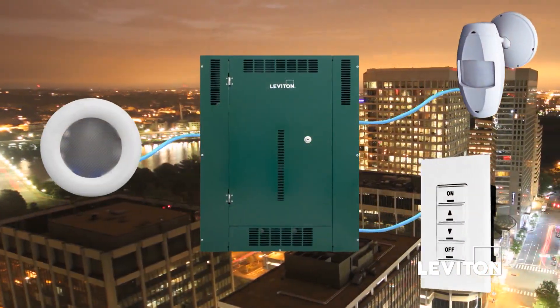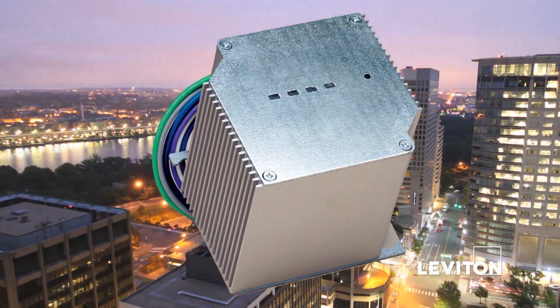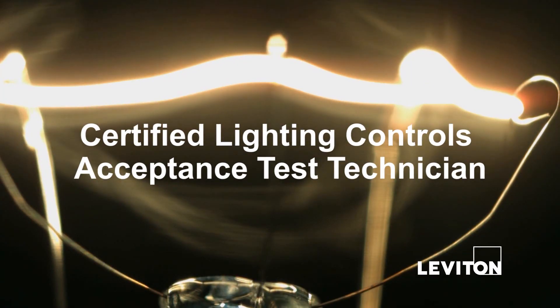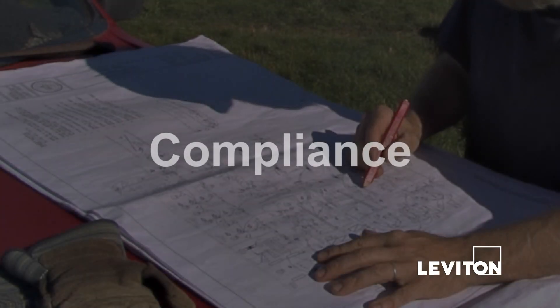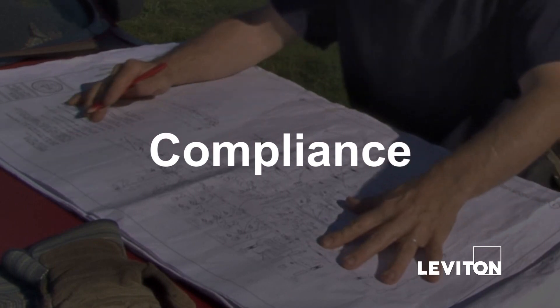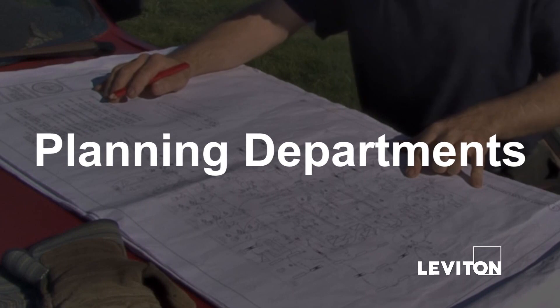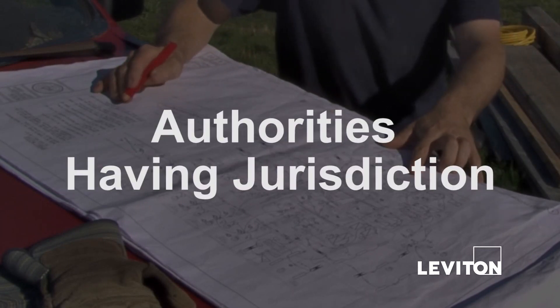Lighting control systems and/or any lighting control devices not listed in the Title 20 database must be tested and approved by a certified lighting controls acceptance test technician. Title 24 compliance is established through certification at the time of inspection, and compliance is policed by planning departments and building inspectors, also known as authorities having jurisdiction.